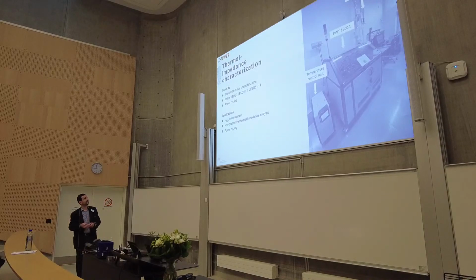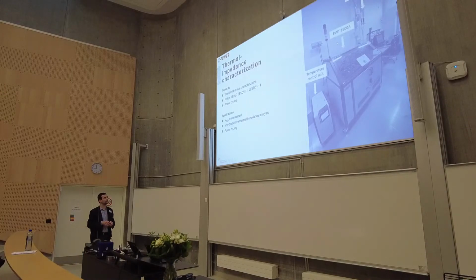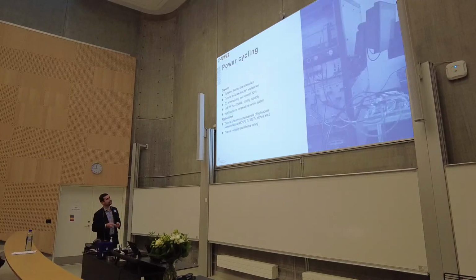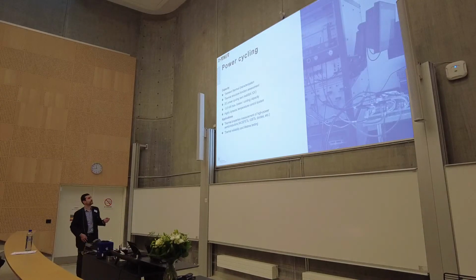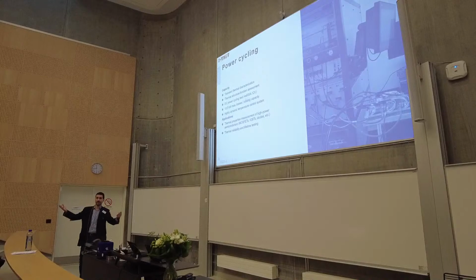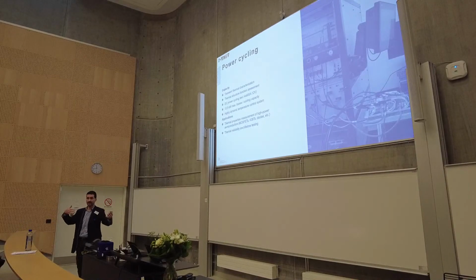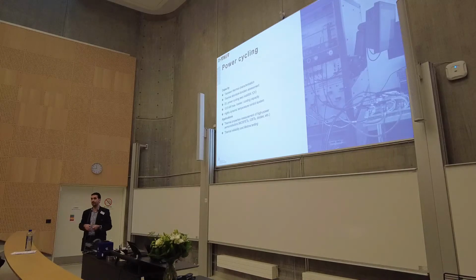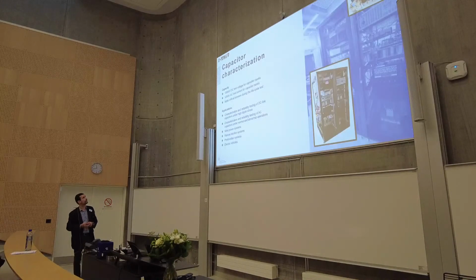This is a relatively high power facility. We are able to run tests up to 1800 amperes at around 12 volts and work out the thermal response. But that's not all - we can reach up to 2400 amperes, with 4 channels of 600 amperes each, for the same goal. We can operate tests in parallel, not just because we have two machines, but because each machine has independent channels we can operate independently of each other.